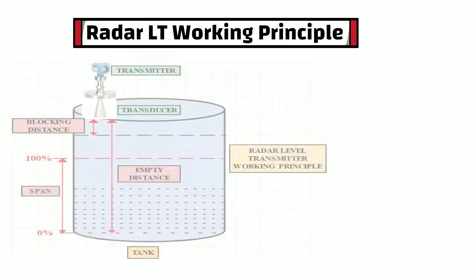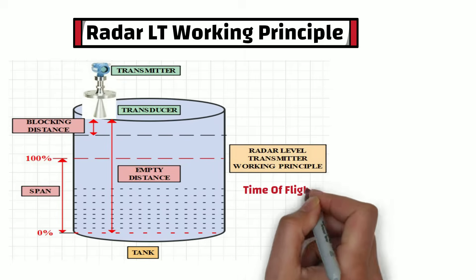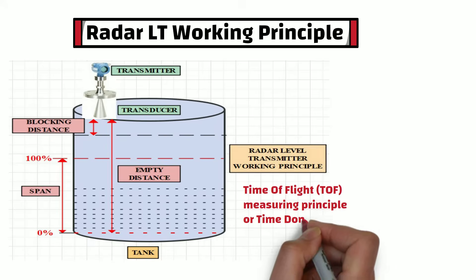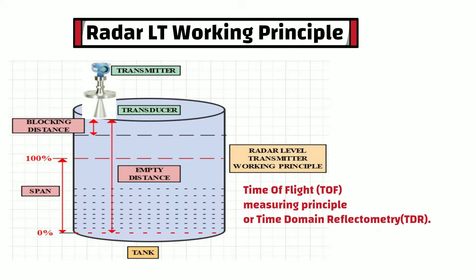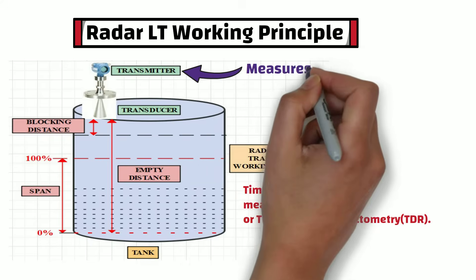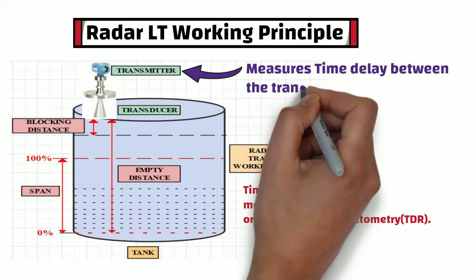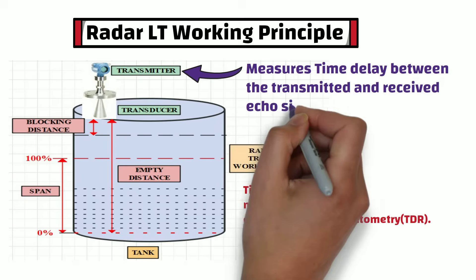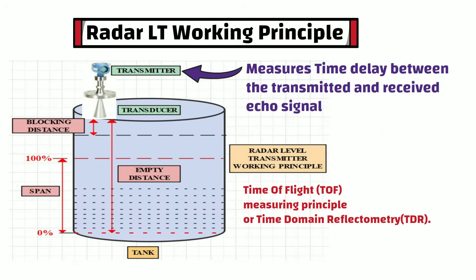Radar level transmitter works on the time of flight measuring principle, or time domain reflectometry principle. In radar level measurement, the transmitter sends high frequency radar pulses traveling at the speed of light towards the bottom of the tank. These pulses bounce off the product surface and return to the sensor. The transmitter's microprocessor then measures the time delay between the transmitted and received echo signal, and calculates the distance to the liquid surface.